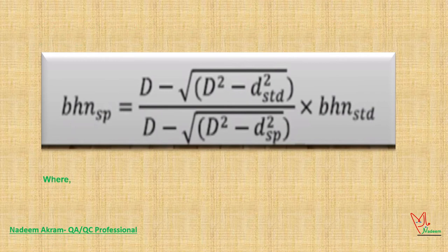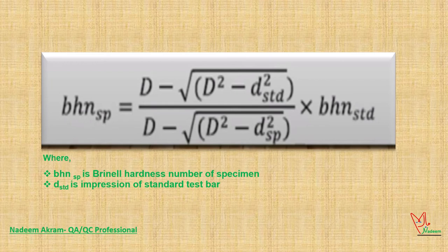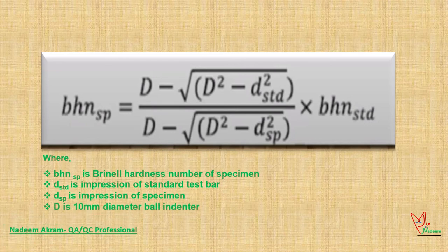BHN SP is Brinell hardness number of specimen. DSTD is impression of standard test bar. DSP is impression of specimen. D is 10 millimeters diameter ball indenter.